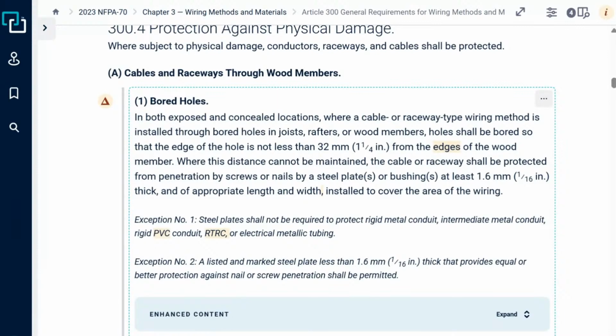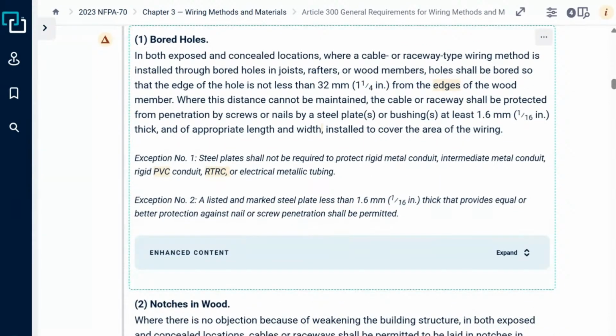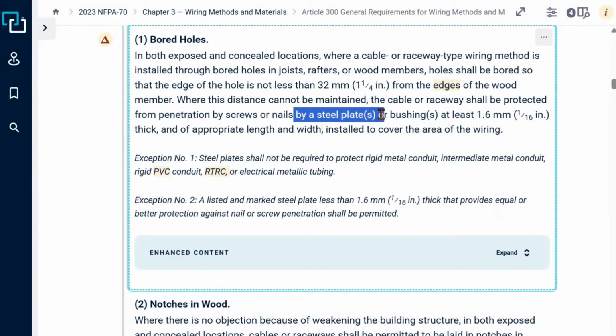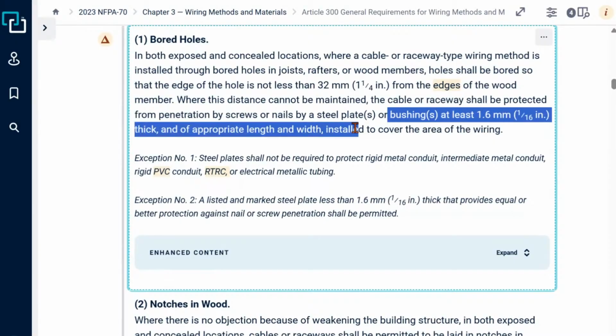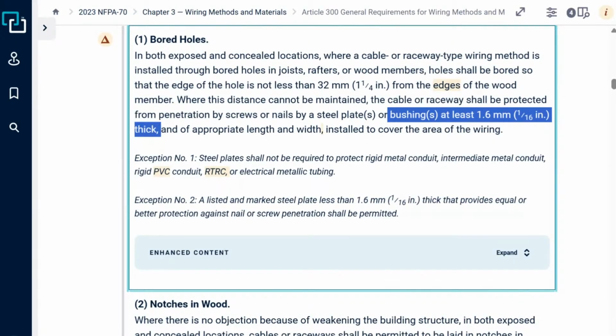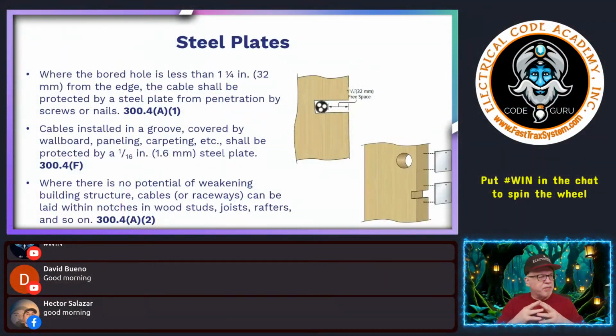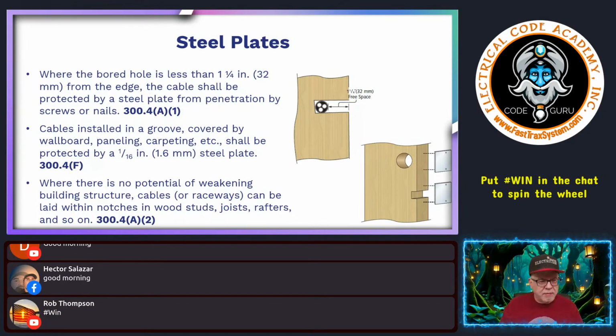So notice it says here about protection by a steel plate, or bushings, at least 1/16 of an inch thick. Many of you have probably seen those little things that slide into the bore hole. We don't have a problem with those as well, I would say they're like bushings. At the end of the day, as long as they provide the thickness necessary, that is 1/16 of an inch, I don't really have a problem with it. Anything that can keep a screw from penetrating it will be all right. I think those little ones that you slide in the holes are a waste, for me, but if you're only going to do a couple, it's not too bad. They are expensive versus just a standard nail plate, but that's up to you, whatever you want to do with that.